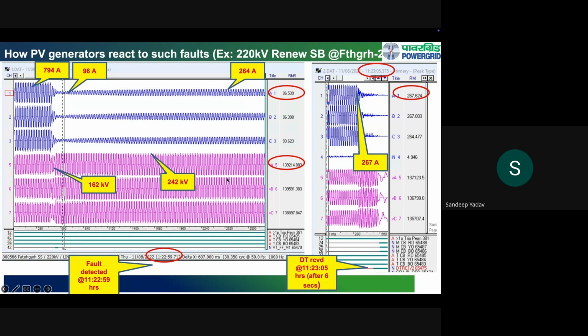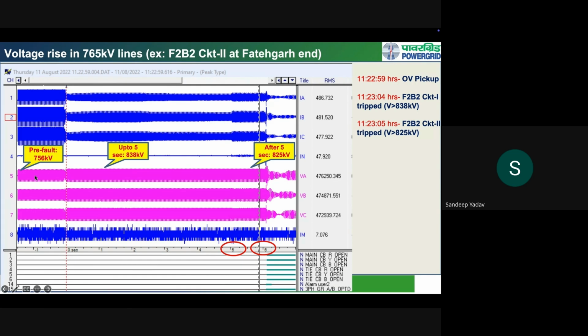because of the drop in the active power, the voltage of the system has risen significantly. If you look at the 765 kV level, the pre-fault voltage was 756 kV, which is close to the rated voltage of 765 kV. As soon as the fault took place, the active power dropped and the system became lightly loaded. The voltage rose to 838 kV from 765 kV, and there is sustained over voltage because the active power is still low. After 5 seconds, which is the time delay for the over voltage protection, the protection operates and trips the line.